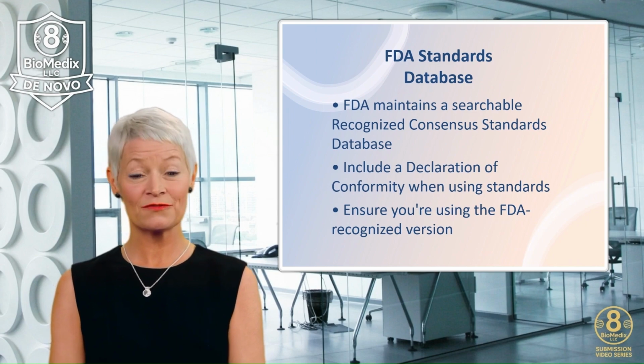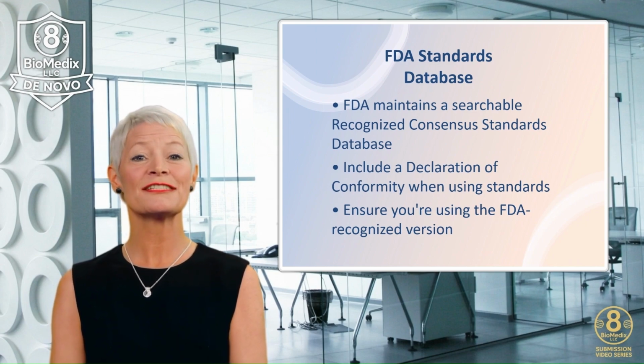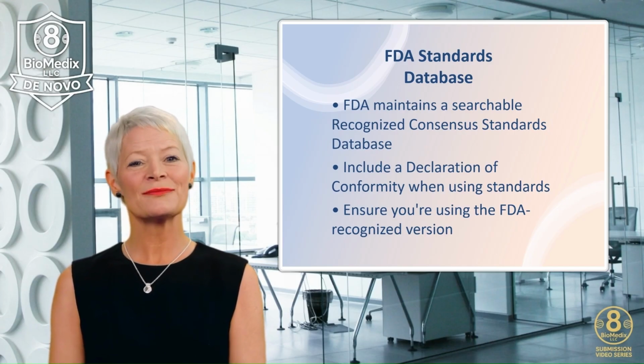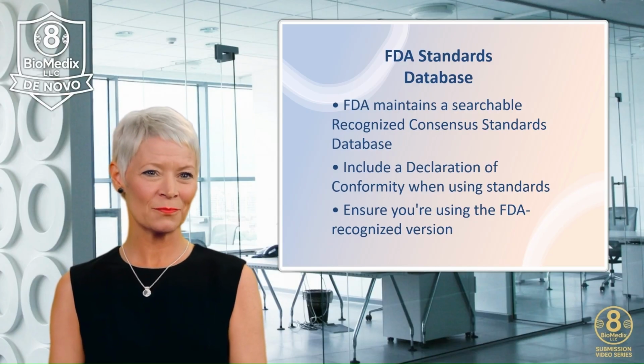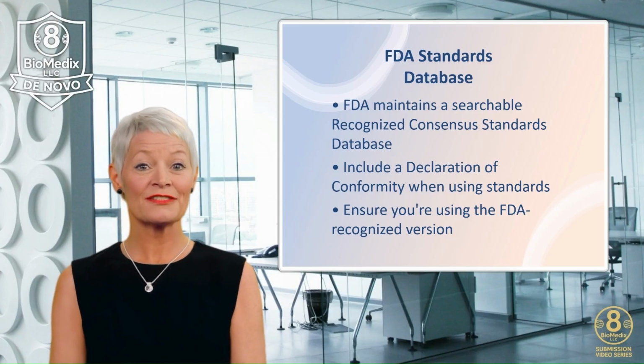When you use a recognized standard, include a declaration of conformity in your submission. This declaration confirms that your device complies with the specified version of the standard. Using standards can streamline the FDA review process and reduce the amount of additional data the FDA may request.